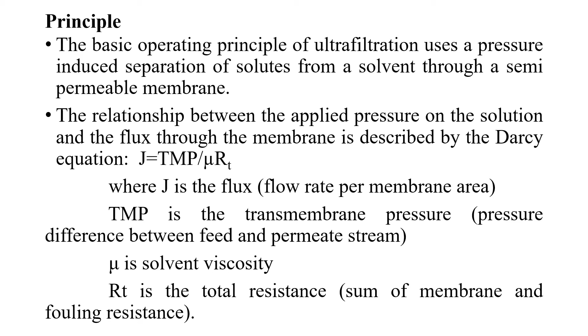In this equation, J is the flux or the flow rate per membrane area, TMP is the transmembrane pressure, that is the pressure difference between the feed and the permeate stream, μ is the solvent viscosity and R is the total resistance. The total resistance is the sum of the membrane and the fouling resistance. So the factors that influence the flow rate are the transmembrane pressure, solvent viscosity and the total resistance that develops.